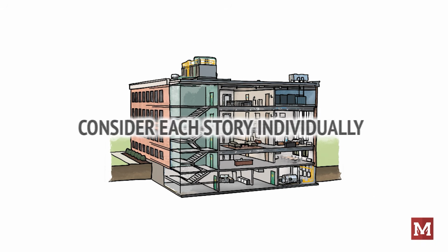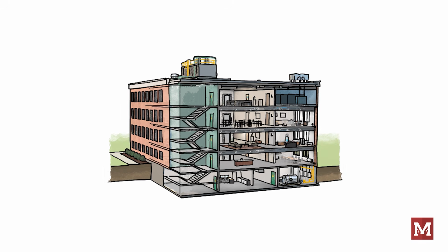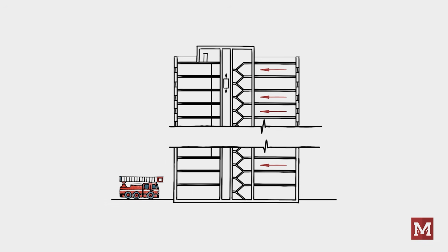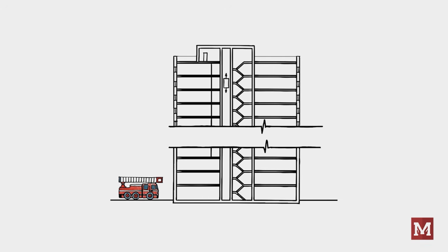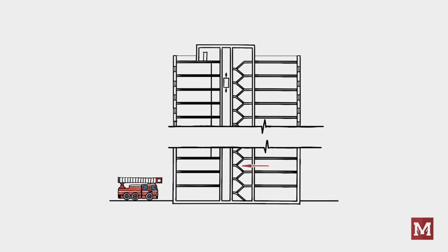Why? If all floors are egressing at the same time and using the same exits, wouldn't there be a traffic jam in the stairs? Fantastic question. The premise behind looking at each story individually is that when the alarm goes off, occupants are in their respective rooms. They will first proceed towards the exit. Now, this is occurring on all floors simultaneously, so no one is in the exit yet. Once the first occupant of, let's say, the third floor reaches the interior exit stair, this is about the same time that the first occupants on the fifth and seventh floor have also reached the exit stair.